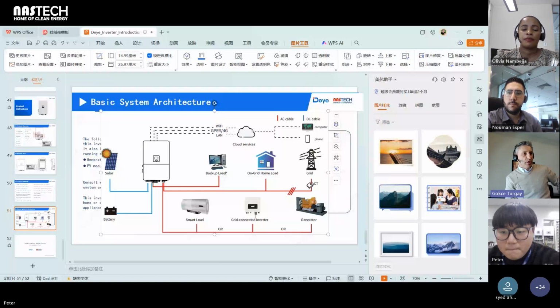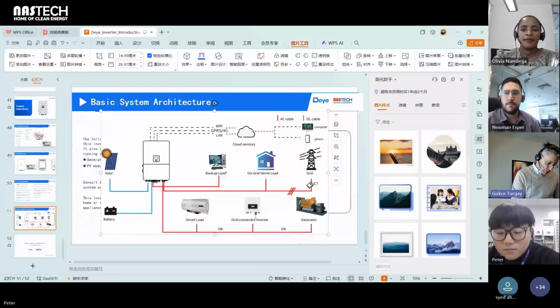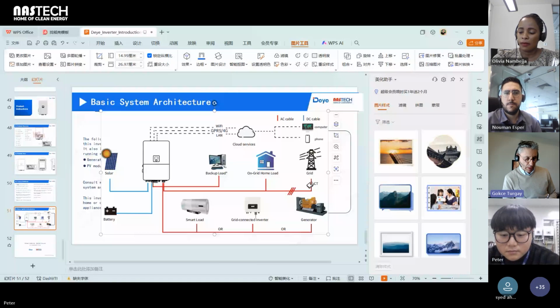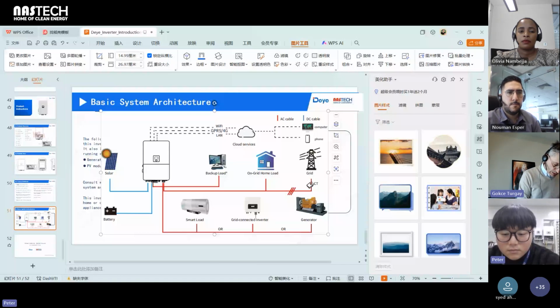This is a big question. I also have some questions. String inverters and DG system, is this applicable without any controller? Is it integrated in the inverter? So in your system schematics, Peter, you mentioned that we will need 2 meters and an ATS to make the string inverters work on an off-grid basis. But actually it is not completely off-grid. You still need the generator to provide, if the grid fails or is down, some kind of a microgrid in the battery line, so then the string inverter can still function. So we will need 2 meters plus ATS plus a generator. Is this correct? Diesel generator.